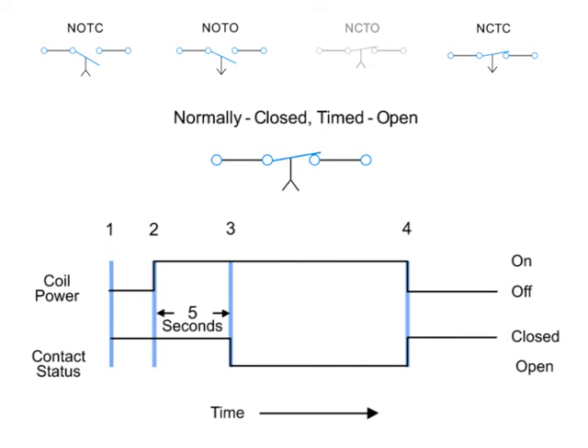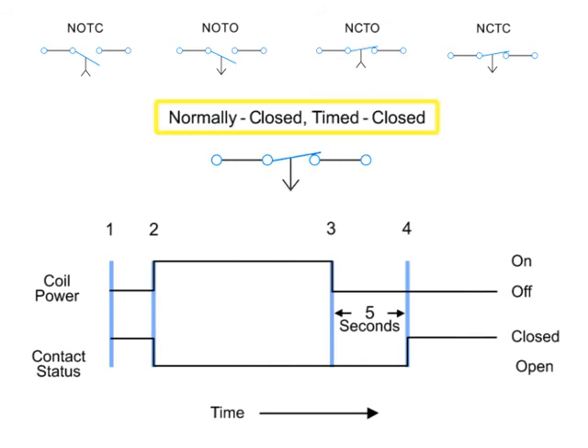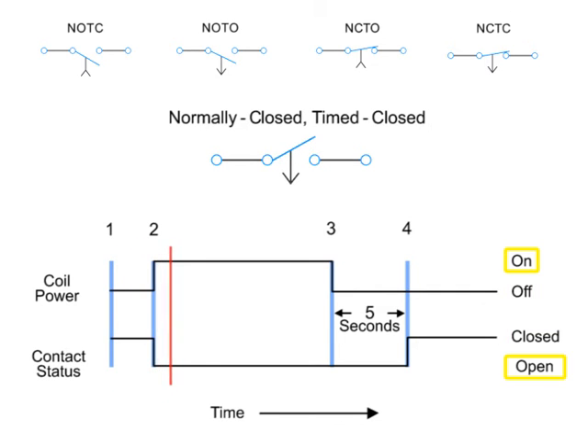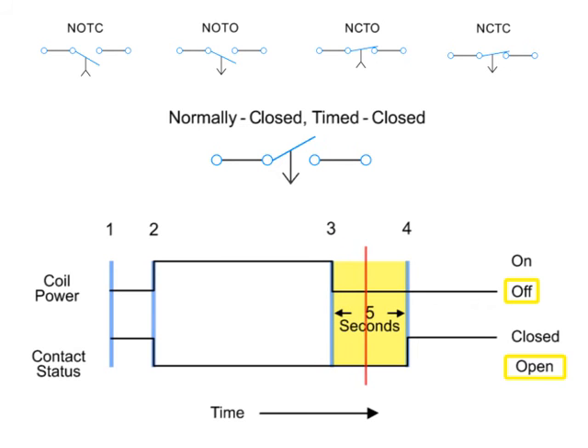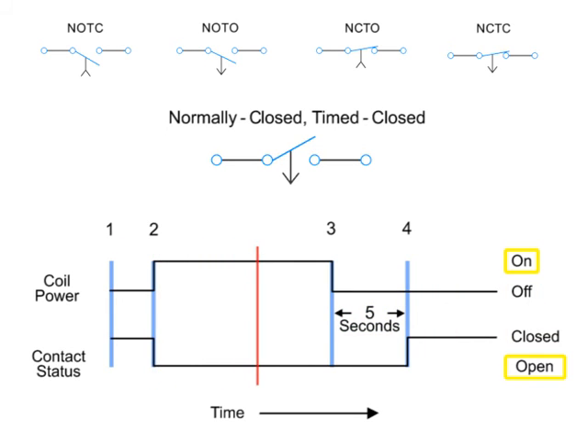The last time delay relay we will look at employs a normally closed, timed closed contact. Similar to the normally closed, timed open contact, this type of contact is normally closed when the coil is de-energized and opened by the application of power to the relay coil. However, unlike the NCTO contact, the timing action occurs when the coil is de-energized instead of when it is energized. Thus, the contacts open immediately when the coil is energized and close five seconds after the coil is de-energized.